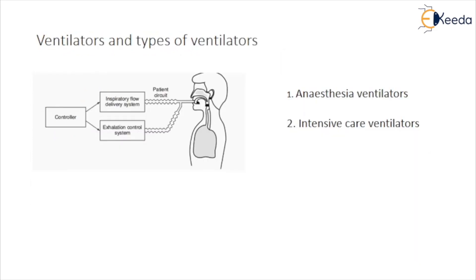When artificial ventilation needs to be maintained for a long time, a ventilator is used. Ventilators are also used during anesthesia and are designed to match the human breathing waveform pattern. These are sophisticated equipment with a large number of controls which assist in maintaining proper and regulated breathing activity. For short-term or emergency use, resuscitators are employed, which depend upon mechanical cycle operation and are generally lightweight and portable.